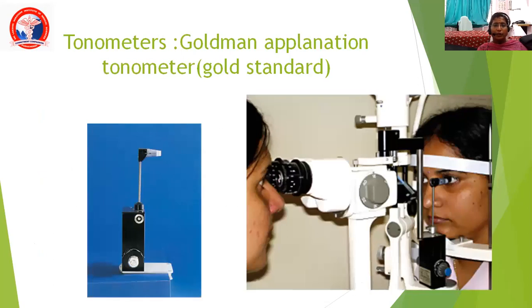These are the tonometers. The picture shows the Goldmann Applanation Tonometer, which is the gold standard. It is usually slit lamp mounted; it touches the cornea and gives two semicircular lines. The reading is taken when the two inner aspects of the two semicircular lines meet together. The disadvantage is that it touches the cornea.